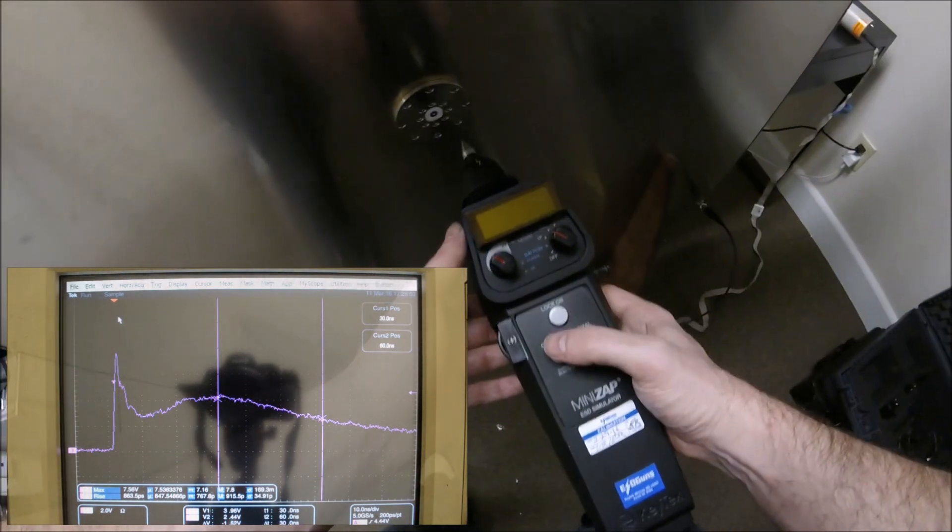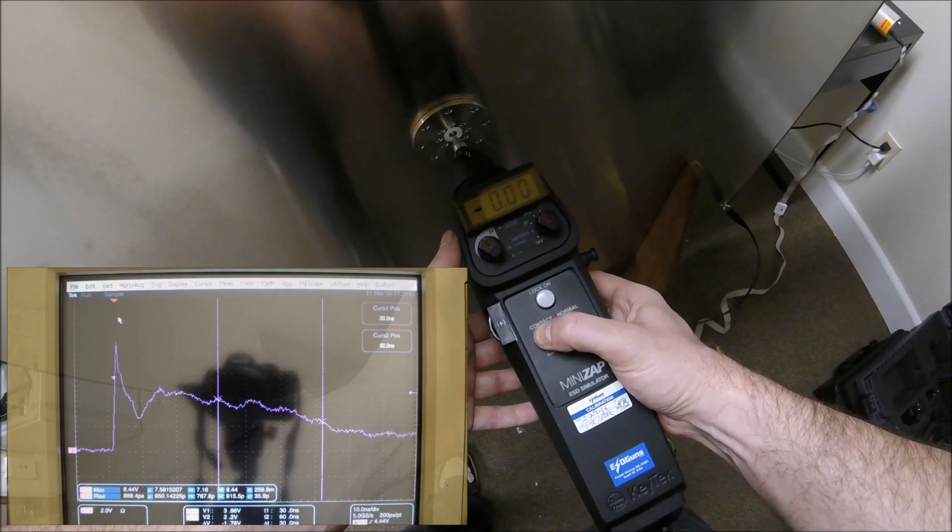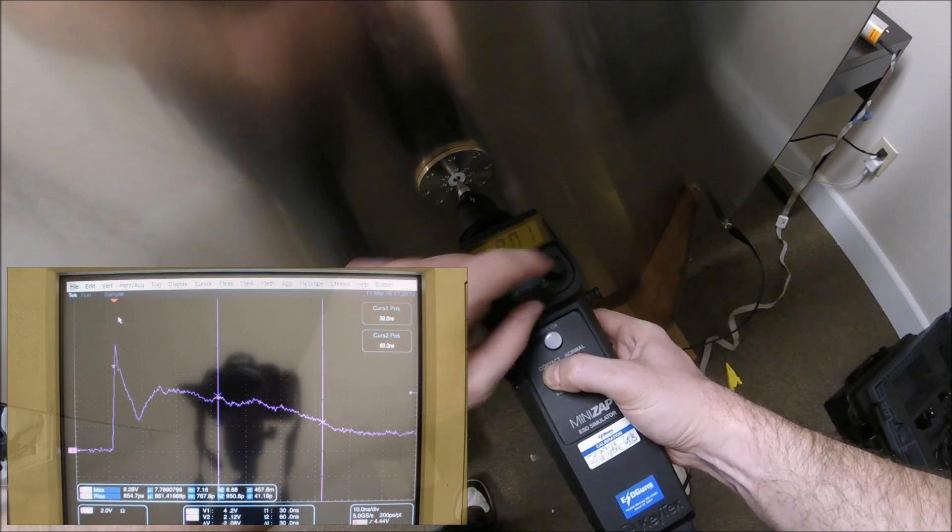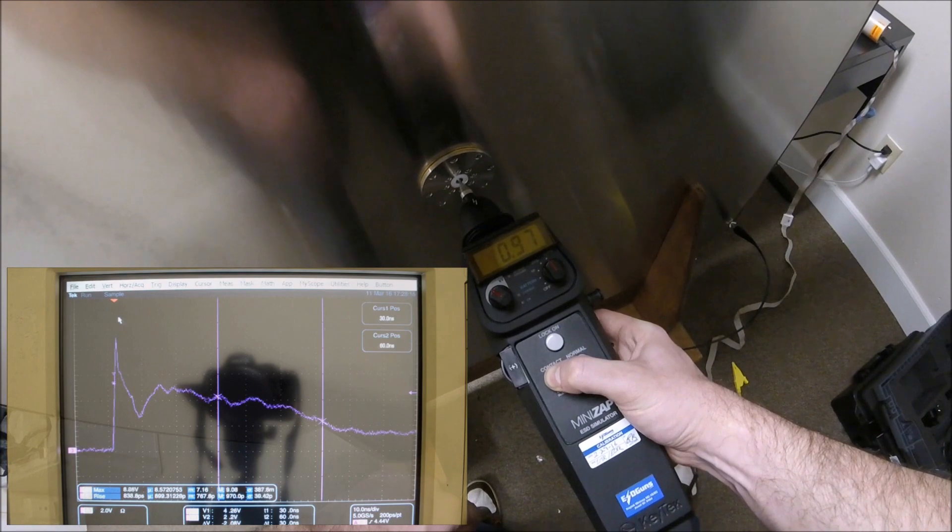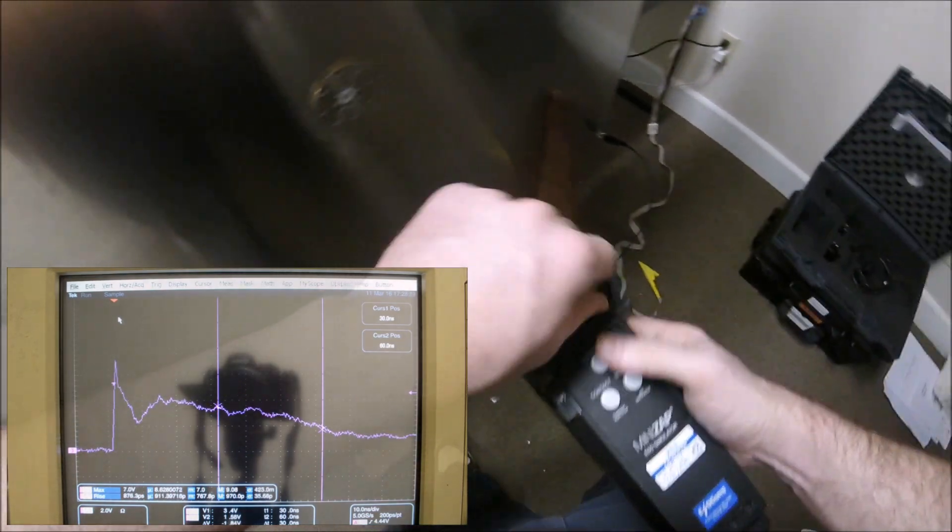The MiniZap and the ESD3000 are the only two units that come with the capability to run through the supplied AC adapter, whereas all the other units you can do this, but you would have to buy an add-on accessory to run it through AC. Otherwise, they run on battery.